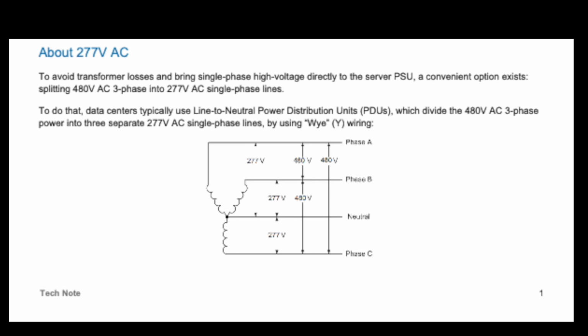Here is a document from Dell about power supplies in data centers. And you see they use now 3-phase 277 or 480 volts. 277 is from each phase to ground or to neutral, and 480 volts is from each phase to any other phase.